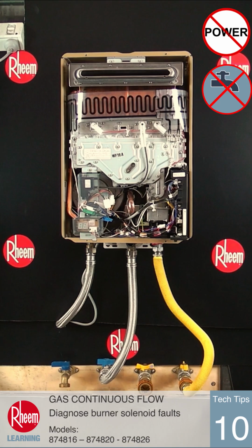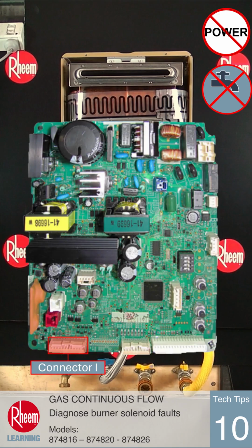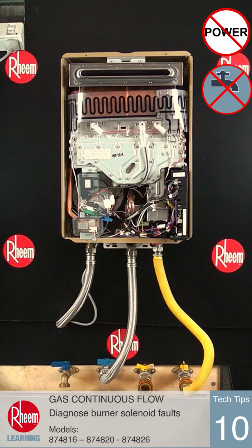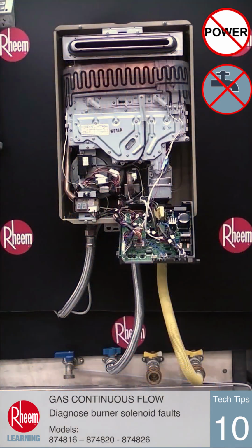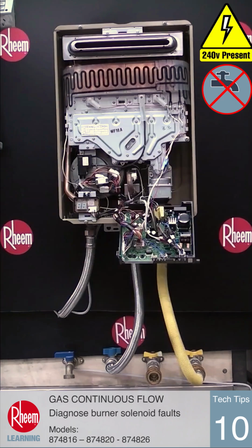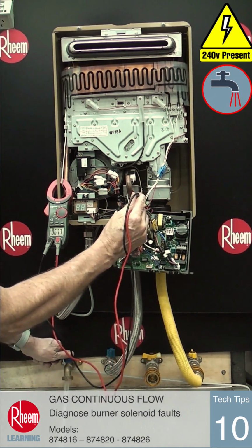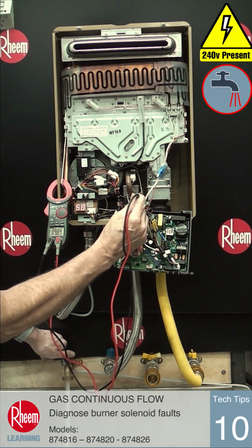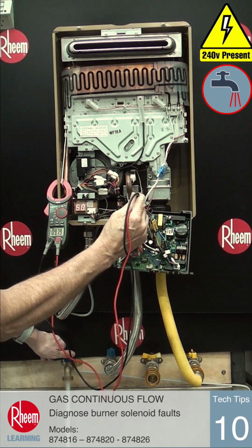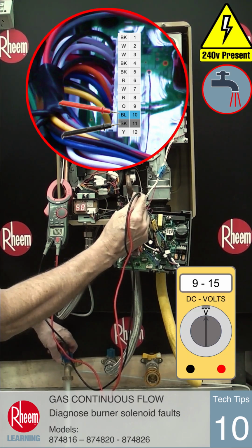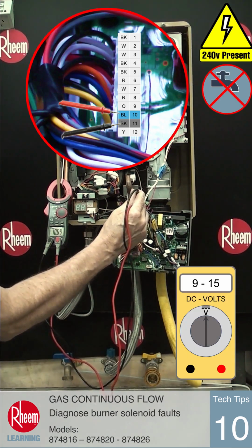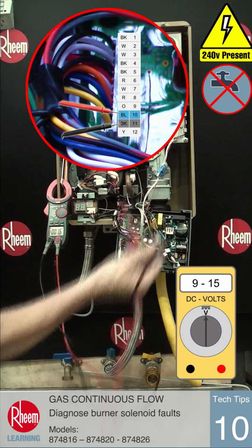The solenoid tests can be done from connector I on the PCB, which will need to be withdrawn from the unit to gain access. This multi-plug wiring connects to all the gas control solenoids and the PGFR, as well as the spark ignition box. To test solenoid 1, turn power on and have water flowing, then use a test meter to measure voltage between pin 11 black and pin 10 blue. The reading should be between 9 and 15 volts DC.